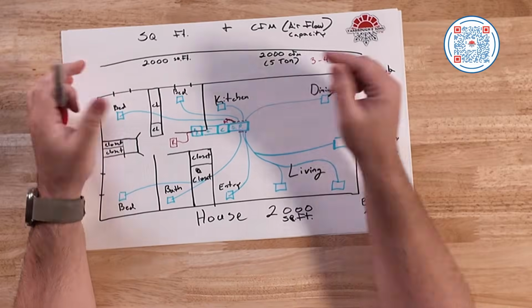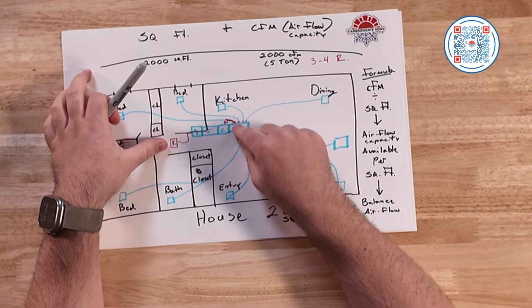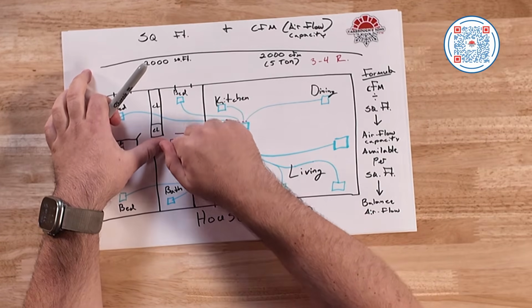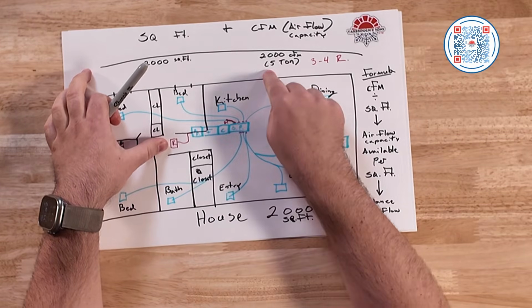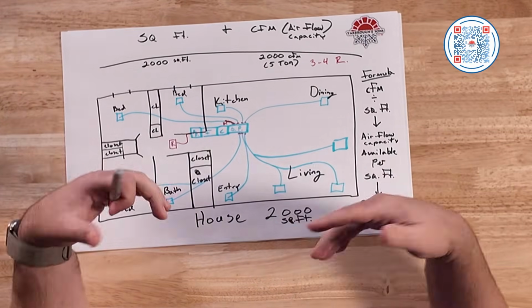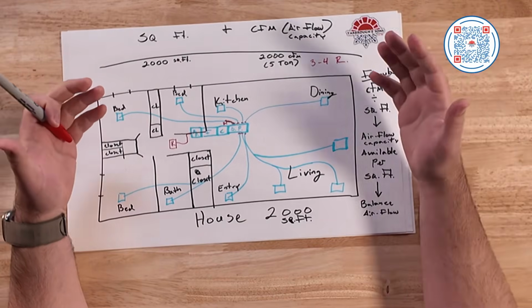I've seen where a return air is only delivering 1,000 CFM back to that unit at a 0.05 static pressure. I want to make sure that that return air is sized appropriately for 2000 CFM. If it's shy, the supply ductwork is going to struggle providing that airflow to each one of those rooms, and oftentimes increasing it will help with the balancing as well.